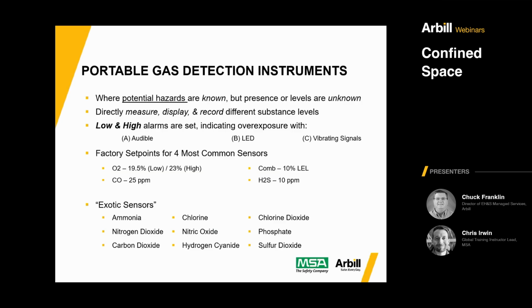So just a little info on what the gas detectors can do and just some of the sensors that are in them. The first thing I really need to say about gas detection is the detector is only looking for what it actually has sensors for. In other words, there is something out there that's called a mass spectrometer, where it's a giant machine as big as a room, where you could put any kind of gas in there and it could tell you exactly what that gas is and in what quantities. Your portable gas instrument is not that. You need to have an idea of what is potentially in the space or what might be lacking in the space in the case of oxygen, so that you've got the proper sensors to search for those things.